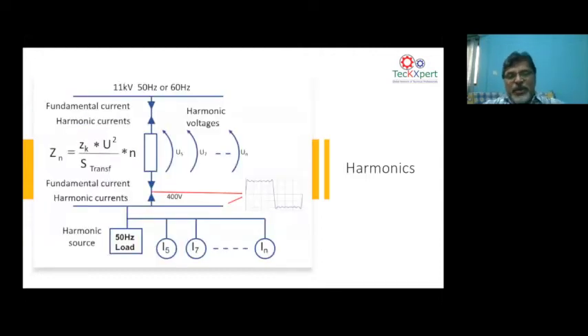Now this is important. This is a very important aspect when it comes to understanding harmonics. As you can see here, you have the load which is producing harmonic currents, and then you have a transformer sitting on the top. Now the whole impedance of the transformer and the impedance of the network creates the harmonic voltage. The very fundamental equation that defines the harmonic voltage is governed by this equation. It all goes by the network impedance. Zn is the network impedance. You calculate that network impedance by the percentage impedance of the transformer, the voltage square, and the kVA of the transformer. That is how you calculate the network impedance. Go to the next slide.